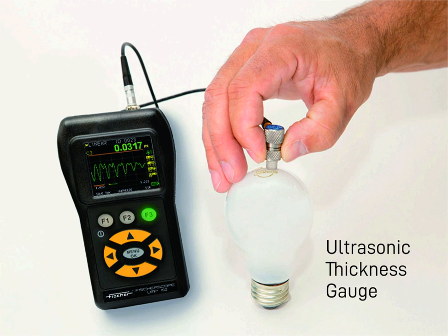Topic: Digital thickness gauge typical usage. UTM is frequently used to monitor steel thickness in various places of ships and offshore constructions. Surveyors equipped with portable UTM probes reach steel plating in sides, tanks, decks and the superstructure. They can read its thickness by simply touching the steel with the measurement head.